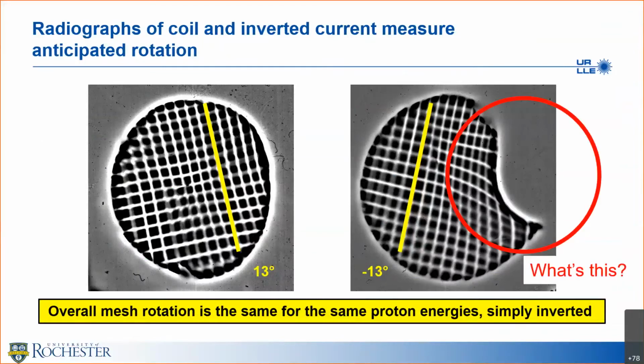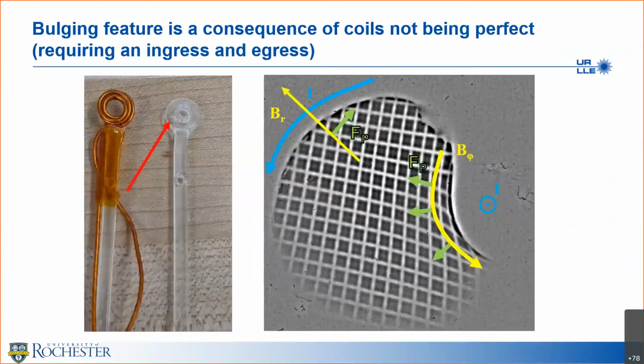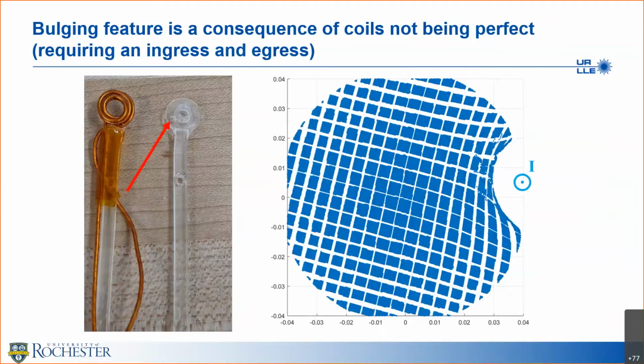Although I have to point out, what is this thing sticking out to the side? That's actually a bulging feature. That's a consequence of coils not being actually perfect when we wind them. We have a hole that requires an ingress and egress for the wire, where the wire is coming out of the plane of the radiograph. Typically you would have current flowing through a wire going out here. This has a radial field going in this direction, and the force on the proton would kick the rotation this way. If we have a wire coming out of the board, you have an azimuthal field, which causes a squeezing of the protons, a force in this direction. And we can simulate that as well. We can stick a piece of wire vertically with the same current and show that it creates the same features that we see.